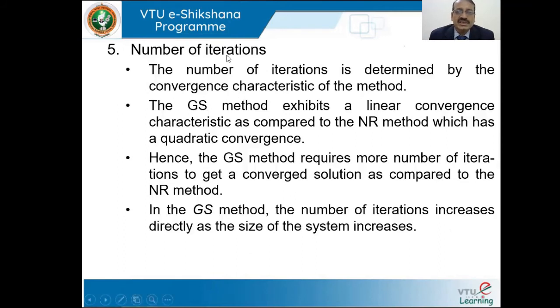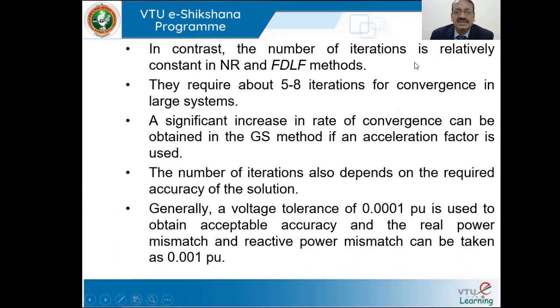Number of iterations: the number of iterations is determined by the convergence characteristics of the method. The Gauss-Seidel method exhibits a linear convergence characteristic, as compared to the NR method which has a quadratic convergence. Hence, the Gauss-Seidel method requires more number of iterations to get a converged solution as compared to the NR method. In the Gauss-Seidel method, the number of iterations increases directly as the size of the system increases. In contrast, the number of iterations is relatively constant in NR and FDLF methods, requiring about 5 to 8 iterations for convergence in large systems.